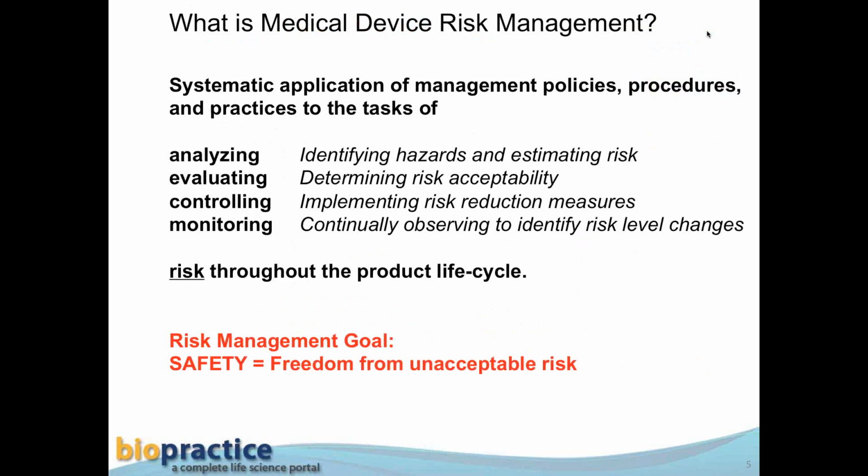Oftentimes I'll run across companies and people who say, hey, we need to do the risk analysis or the risk assessment. Well, that's only a portion of the overall risk management process, so please keep that in mind. So what's the overall goal? The overall goal of risk management is medical device safety, freedom from unacceptable risk. It doesn't mean no risk, because as we know, for some products, risk is inherent. Even the mechanism of action can have a risk aspect. The bottom line here is you need to ensure in the end that the benefit of the medical device exceeds the risks.